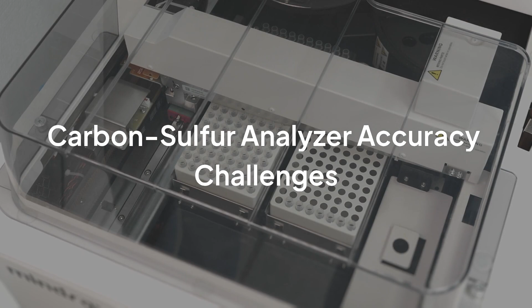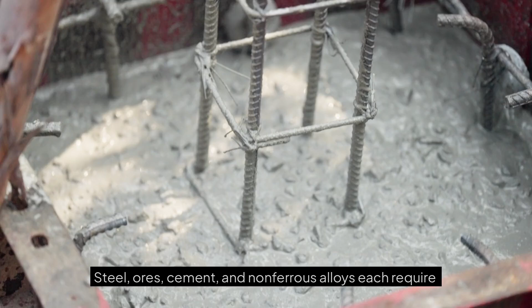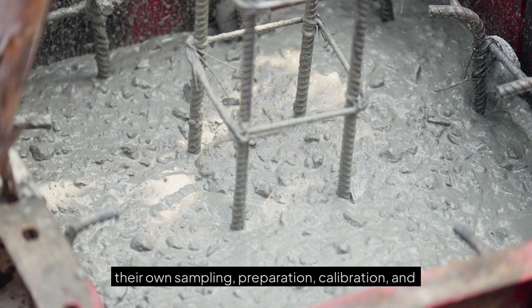A carbon-sulfur analyzer can produce a highly repeatable result and still report the wrong answer, if the portion tested does not represent the material, retains uncontrolled moisture, or fails to combust completely. That is why broad material compatibility must never be confused with a validated method. Steel, ores, cement, and non-ferrous alloys each require their own sampling, preparation, calibration, and verification controls.